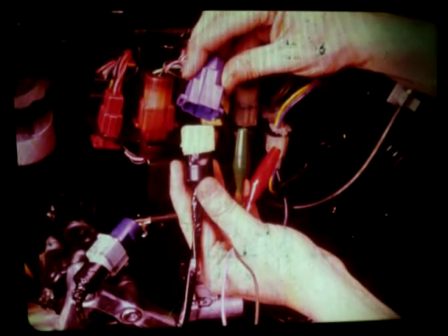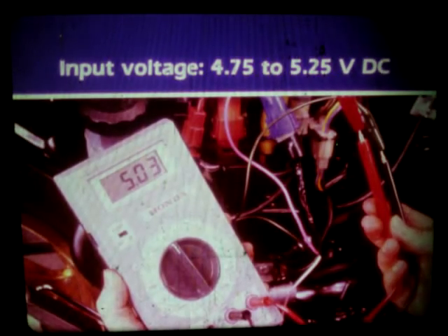Hook up the special adapter to the PB sensor connector and the main wiring harness. Attach the multimeter's red probe to the adapter's pink lead, and the black meter probe goes to the adapter's green lead. Set the multimeter to the 20-volt DC scale and turn on the ignition. The voltage reading should be between 4.75 and 5.25 volts DC. Sensors PB, P1, and P2 should have the same input voltage.